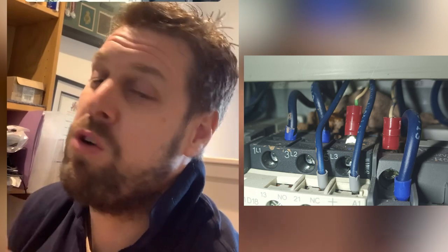Like I say, every time you find something wrong with the safety relay, you've got to rectify it. Even if it's a little bit wee-wah, woo-wah, you're not sure that's what's causing it, it's got to be rectified, because you can't move on, can you? Because there's so much of a pain in the arse, delicate, touchy systems that a contactor that's been run by it with a wasp nest on, picture above, needs to be rectified.